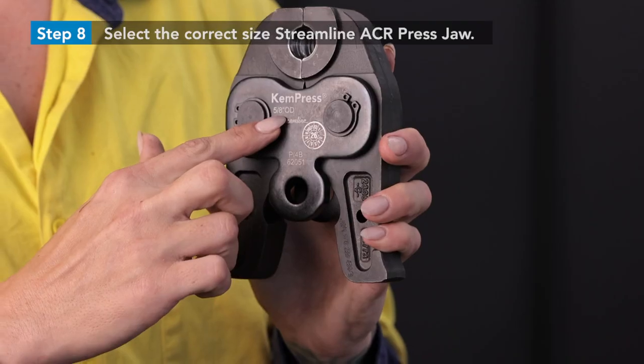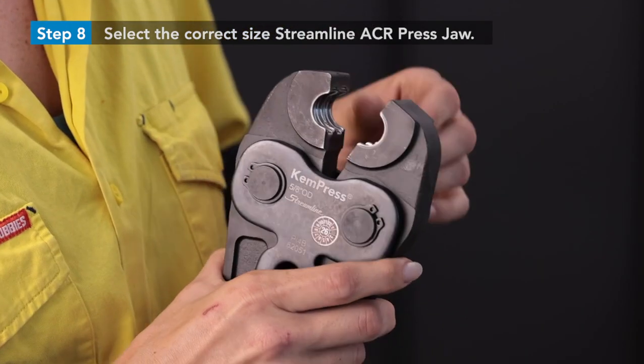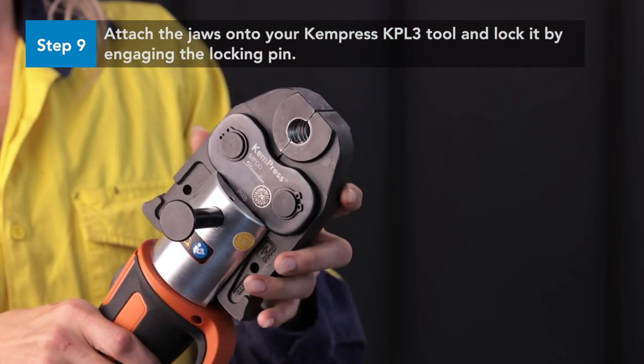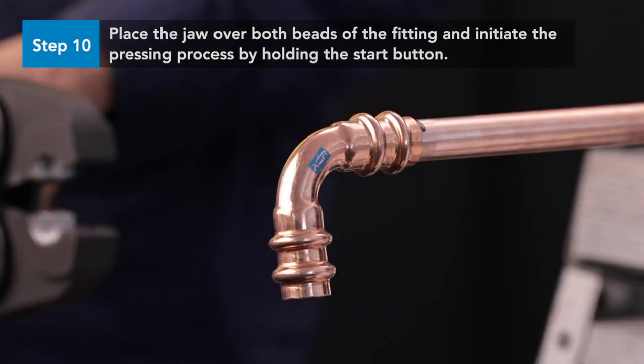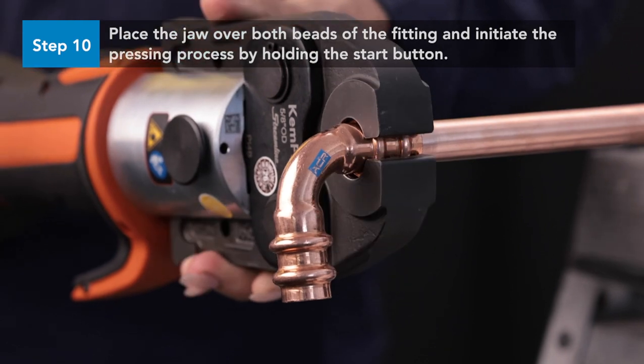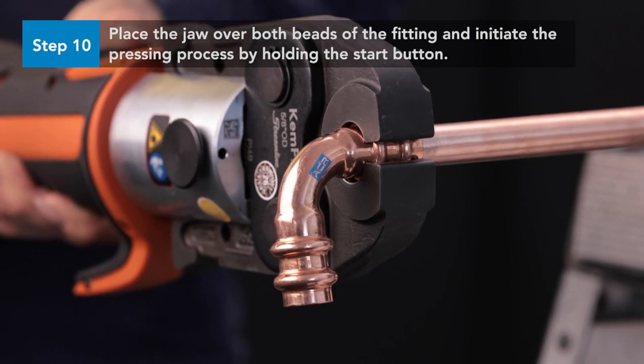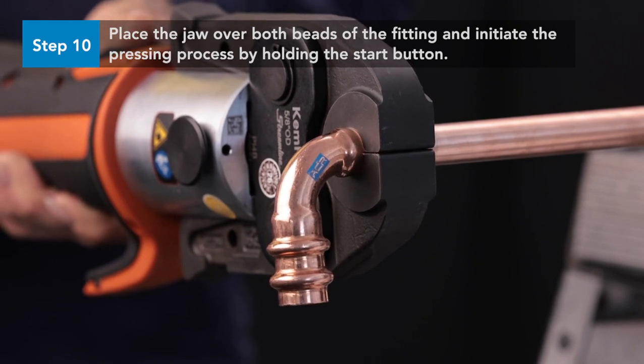Select the correct size Streamline ACR press jaw and check the jaw is in good condition and its pressed surface is clean and free from debris. Attach the jaws onto your KemPress KPL3 tool and lock it by engaging the locking pin. Place the jaw over both beads of the fitting at a right angle to the copper tube. Ensure the two beads of the fitting fit into the two corresponding grooves of the press jaw. Check the fitting is still fully engaged up to the insertion depth mark, and once the jaw and fitting are correctly engaged, initiate the pressing process by holding the start button.